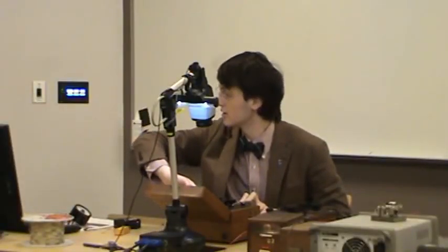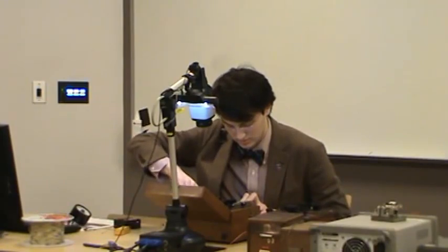There we go. You have to press on both buttons. One enables the galvanometer, the G switch. The other enables the battery. So we deflect our galvanometer. We set these, or our highest range, thousands of ohms, in a fairly high position. Oh, look, we're already getting there. And then once we have it relatively close like that, you start working with your other controls. You can see we're getting closer and closer. That was just hundreds of ohms, now tens of ohms.